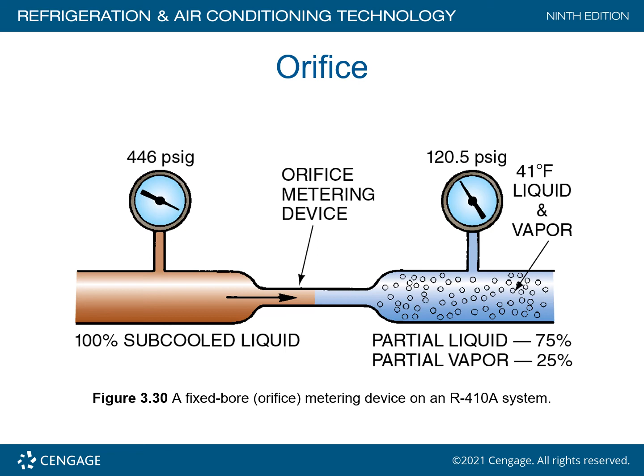And in this case here, we are measuring 120.5 psig. Over here on the liquid, high pressure, high temperature side, 446 psig. And basically what we are looking at in the liquid line is 41 degrees liquid and vapor at 120.5 psig.